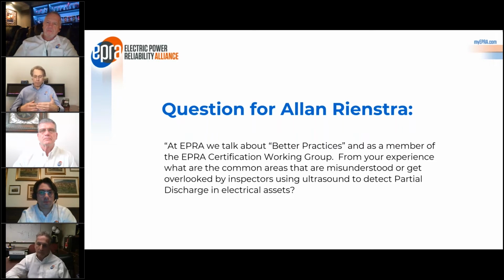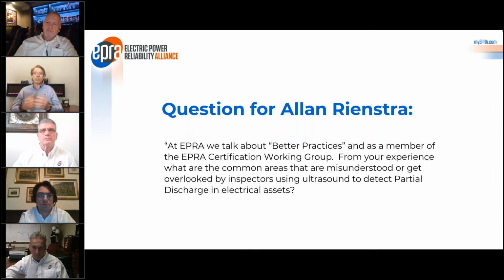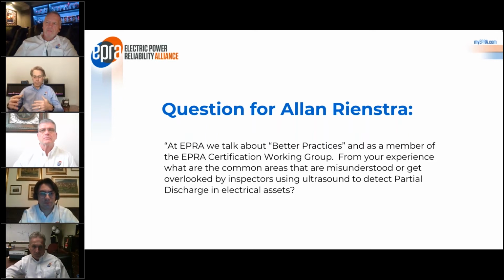For an airborne defect, say corona discharge traveling to us from a transformer or a connection to our sensor, if we want to measure the amplitude or severity of that corona discharge, we can't ignore the inverse distance law. It just says if I measure from 10 meters, 10 yards, or 50 feet today, and come back next week, I need to be at the same distance, because there's an attenuation of signal. The inverse distance law is the biggest mistake inspectors make with airborne inspections.